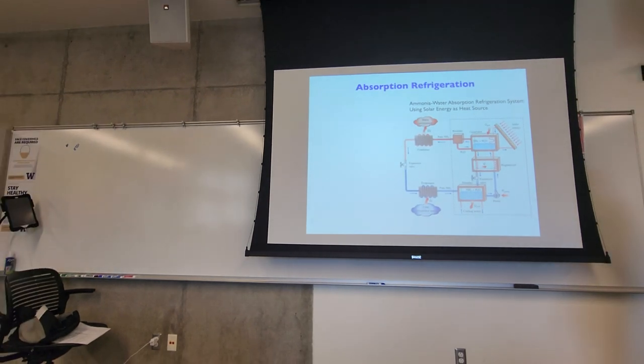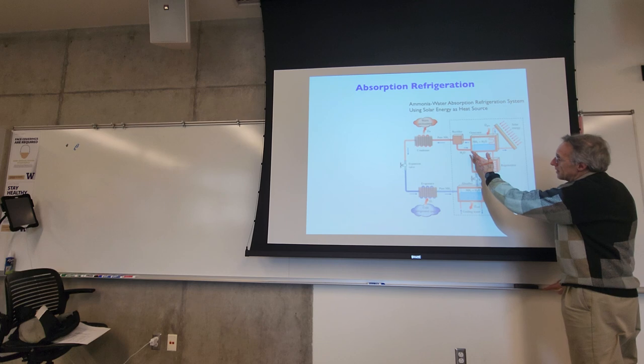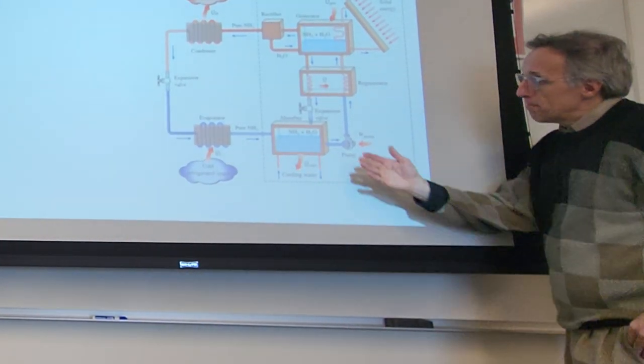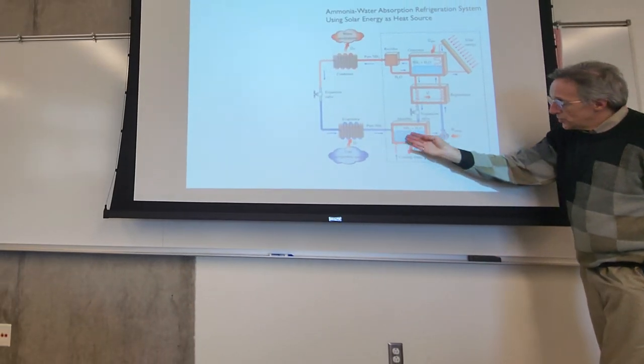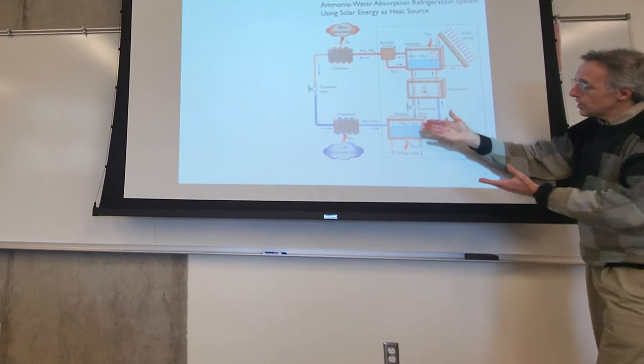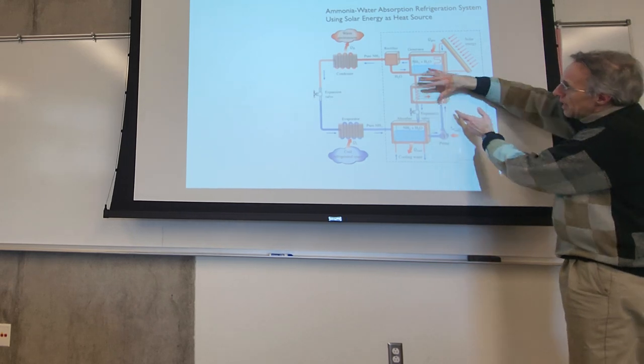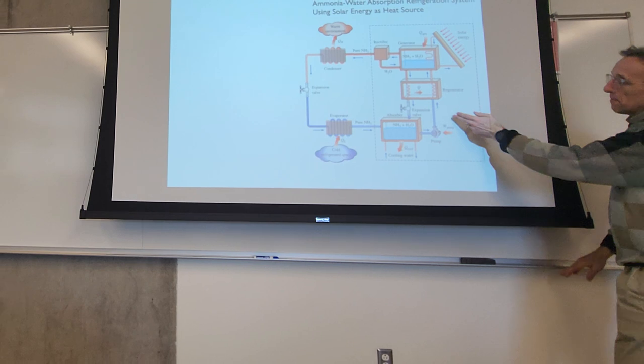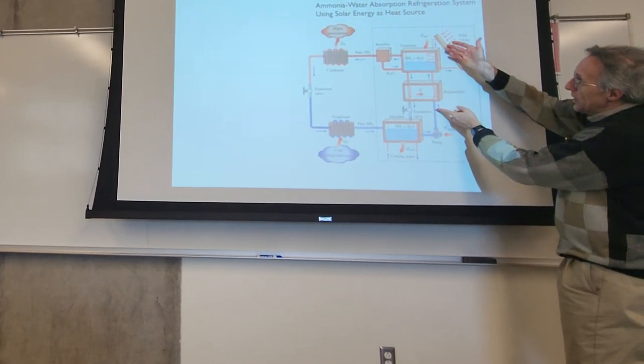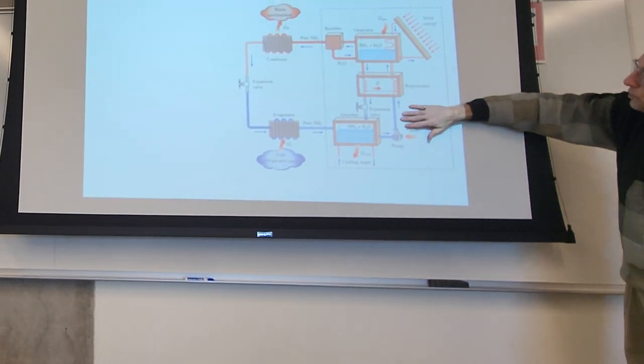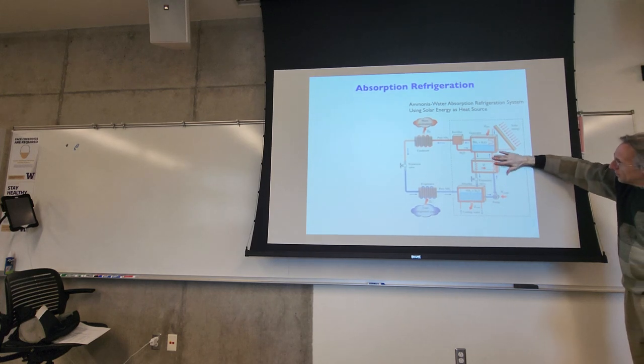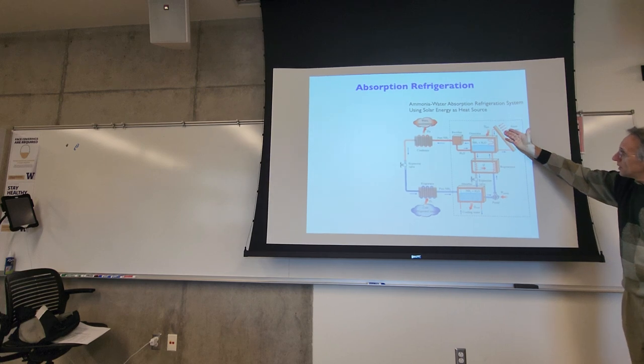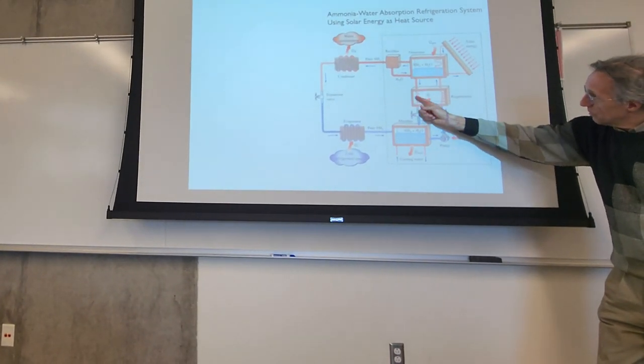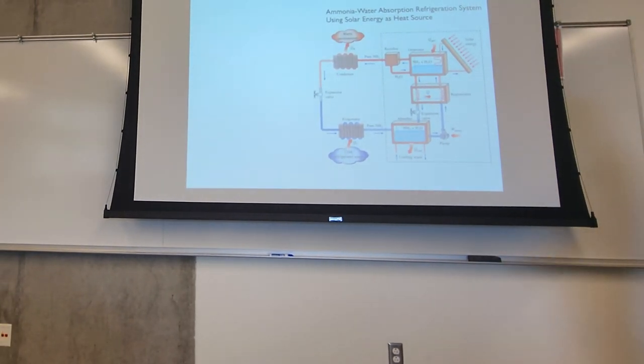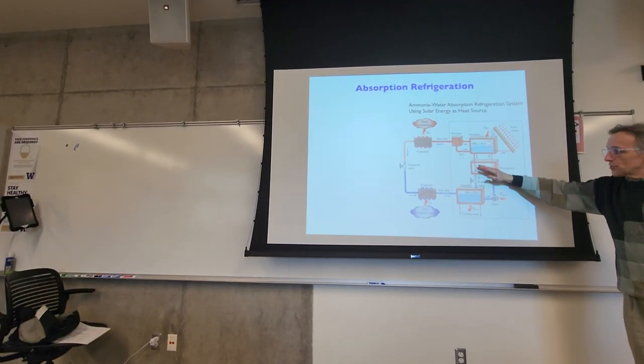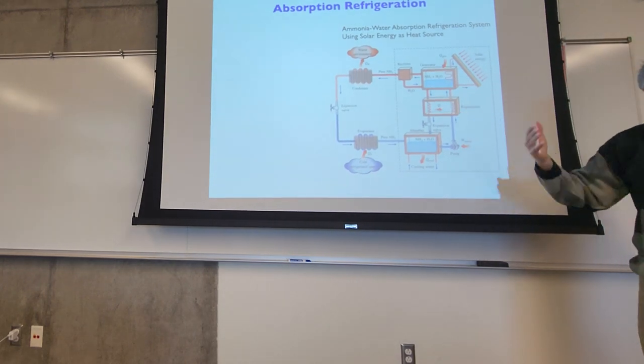You want the water here to be cool, because the colder the water is, the more easily the ammonia is going to dissolve in it. But then it's going to heat up anyway as you heat it. So you want to get this water back down, get it as cool as you can, and so you have this little heat exchanger here. This is convenient because you want this to be hot, because you're heating it. So you get kind of a two-for-one. You preheat the ammonia-water mixture before it goes in. That's going to reduce the energy input here, and because you're transferring heat from this water, you're helping to cool that down. Now, you can run this without this heat exchanger. It's just going to be more expensive because you're going to need more cooling here and more heat there. So this makes it a little more economical.